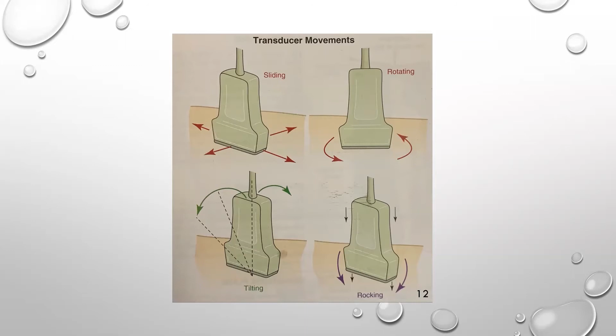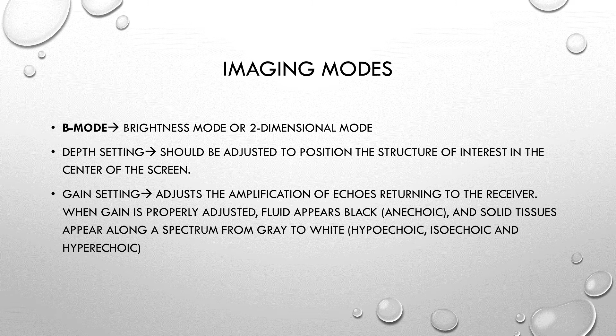We have multiple imaging modes. B mode is brightness mode or two-dimensional mode. That's what usually ultrasound is set to. You can change the depth on this setting. It's adjusted based on the position structure as well as the body habitus of the patient. You can also adjust the gain setting. Gain is basically adjusting the amplification of echoes returning to the receiver. When it's properly adjusted, fluid appears black, and solid tissues appear along the spectrum from gray to white.